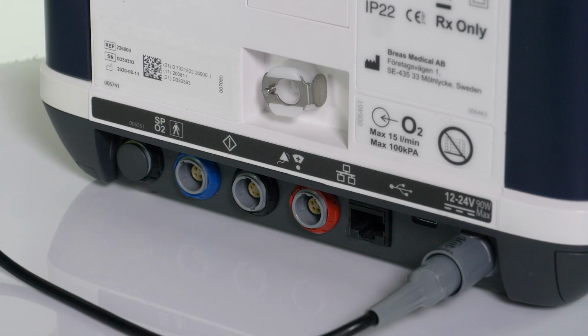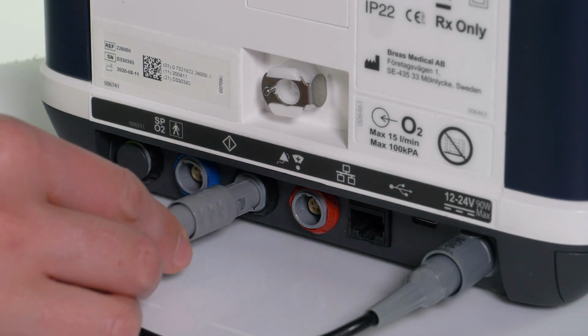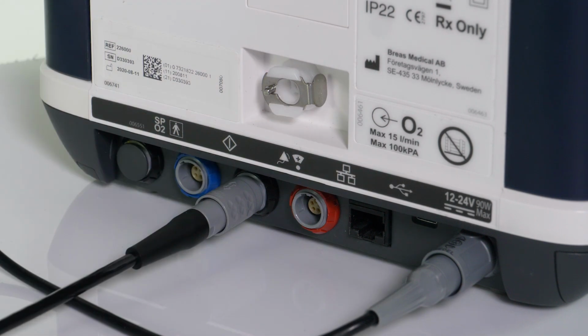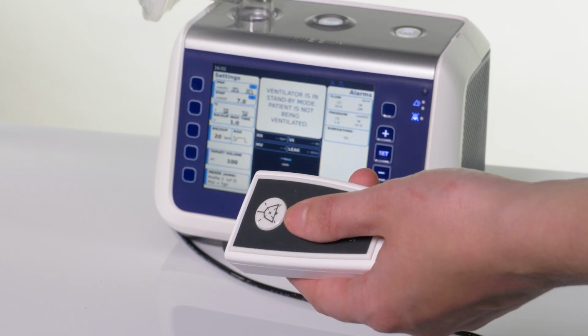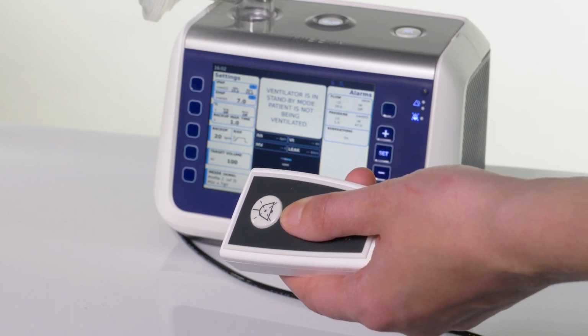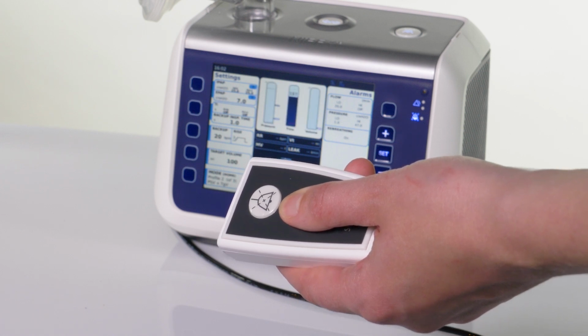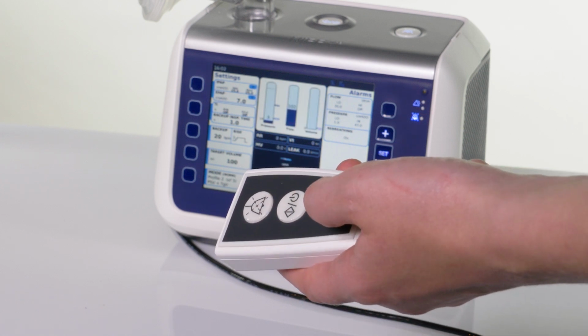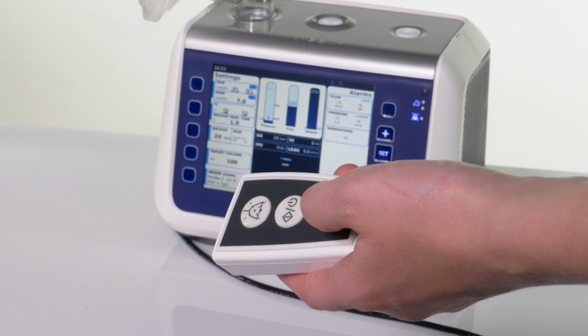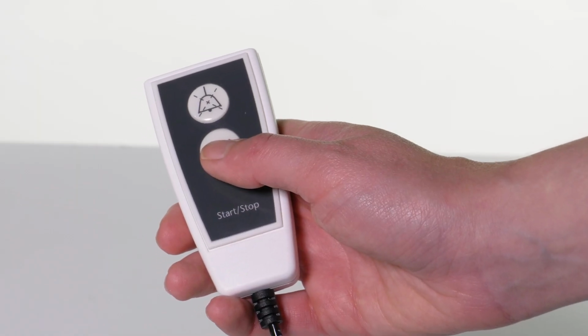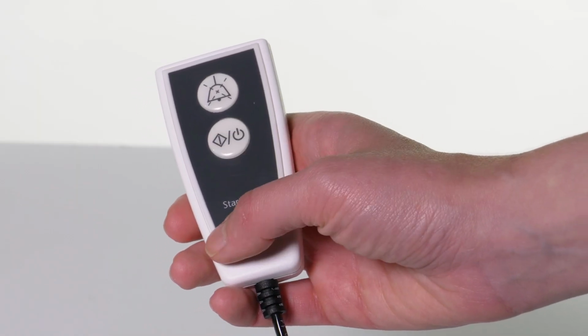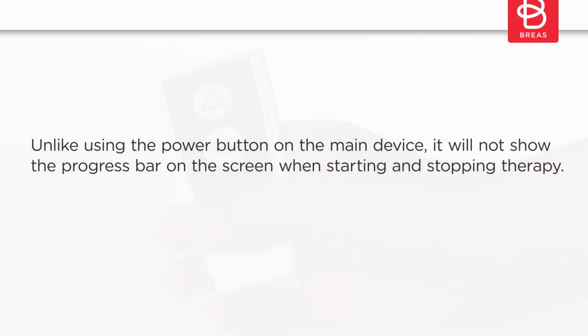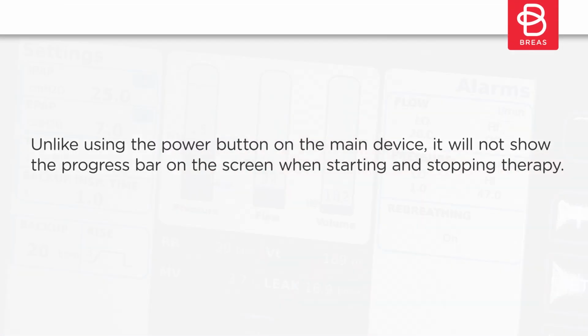Remote Start-Stop button. Plug the remote into the black socket on the rear of the device to use. To start therapy, press and hold the power button on the hand control for 3 seconds. The device will beep when you first press the button and beep twice when the therapy is starting. To stop therapy, press and hold for 3 seconds and then press again to confirm stop. Unlike using the power button on the main device, it will not show the progress bar on the screen when starting and stopping therapy.